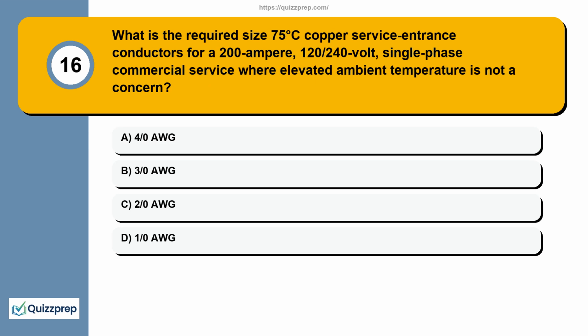Question 16. What is the required size 75°C copper service entrance conductors for a 200 ampere, 120/240 volt, single-phase commercial service where elevated ambient temperature is not a concern? 4/0 AWG, 3/0 AWG, 2/0 AWG, 1/0 AWG.